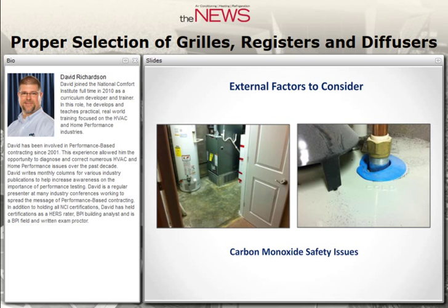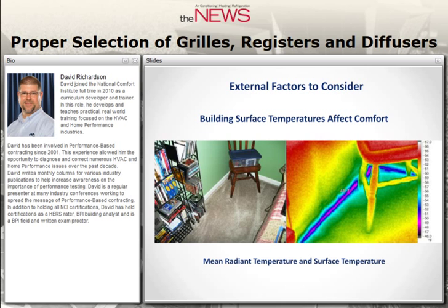Another set of external factors involves carbon monoxide safety. Visual clues can lead us to these issues — for example, a furnace sitting on a box with return grills on the side in an airtight room with a natural draft water heater. That water heater was spilling almost 100% of its flue gas into the room whenever the door was shut due to depressurization effects. Be very careful when changing airflow patterns and pressures within a building, as you could unintentionally create a carbon monoxide safety issue.